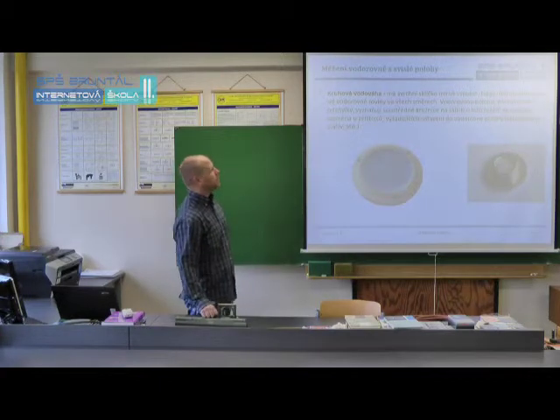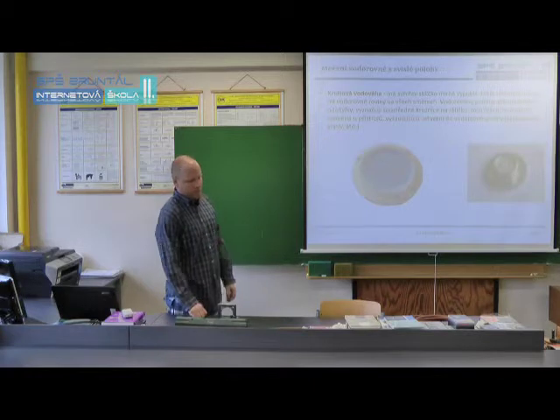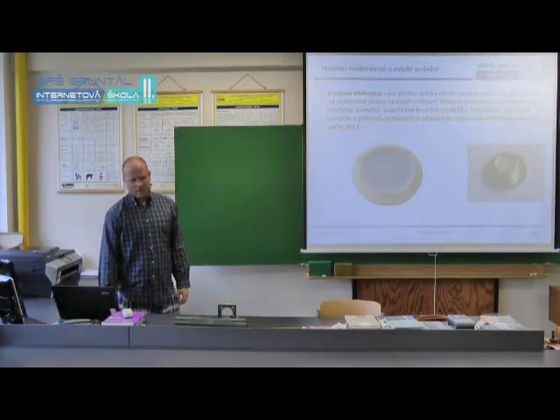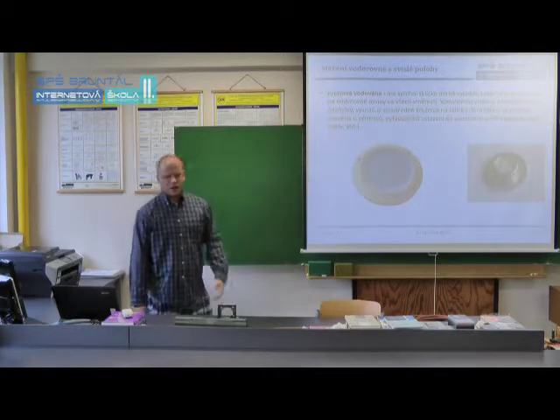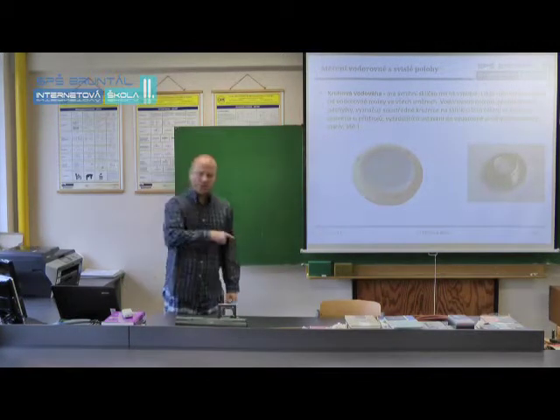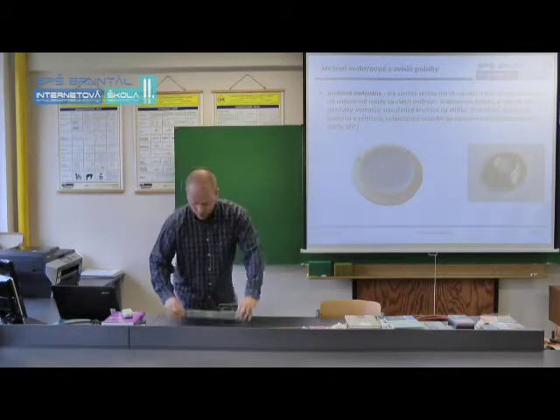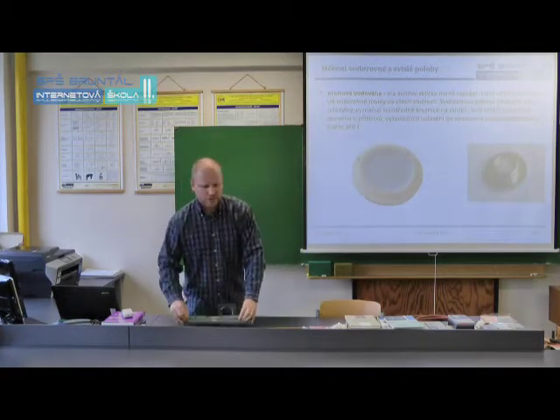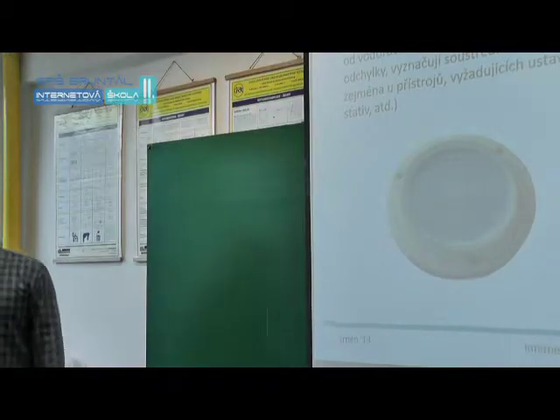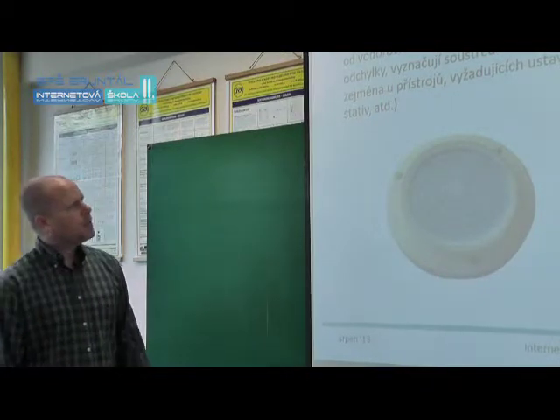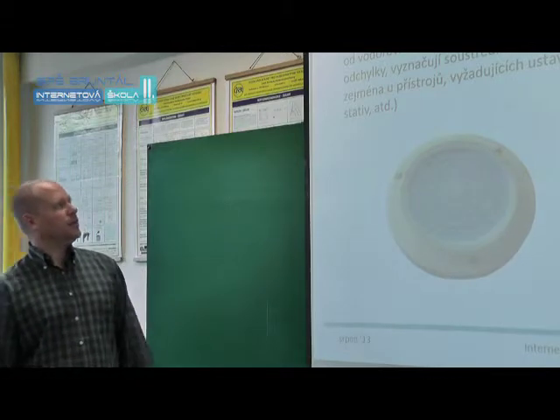Inside is liquid and a bubble. It's used where we want to set machines or measuring equipment to horizontal position from any direction. While with a classic spirit level, even a cross one, we would need to check multiple directions, this circular level reveals deviation from horizontal in any direction. For example, it's used for setting up precision scales or tripods.